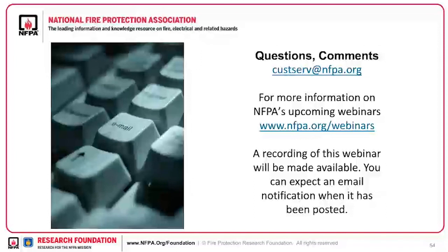Next question, how do you apply the required distance separation and multiple racking? This is a question that comes up quite a bit. When, say, NFPA 855 says an energy storage system greater than 50 kilowatt hours, then you need to have testing. Well, what does that mean, and how far separated things have to be? And so I think that if you have a collection of batteries that exceeds the 50 kilowatt hour, then you need to have separation, or you need to run a fire test to prove that separation isn't needed. There's also a criteria in there that if a fire room has more than 600 kilowatt hours, you should run testing. So probably the simplest way to interpret that would be a single rack should have separation if it exceeds 50 kilowatt hours. That would kind of be in the context of how I ran these tests.